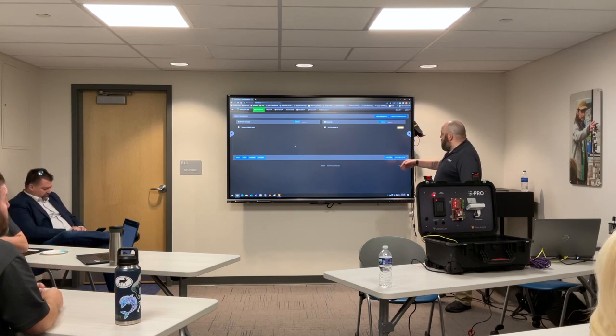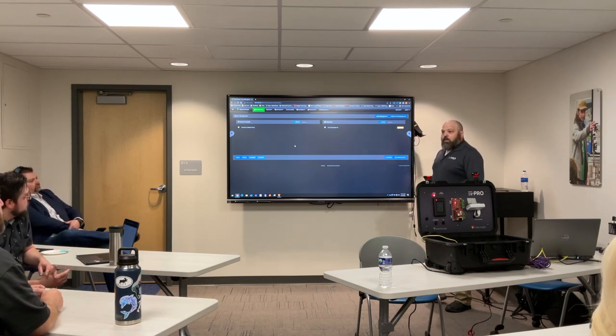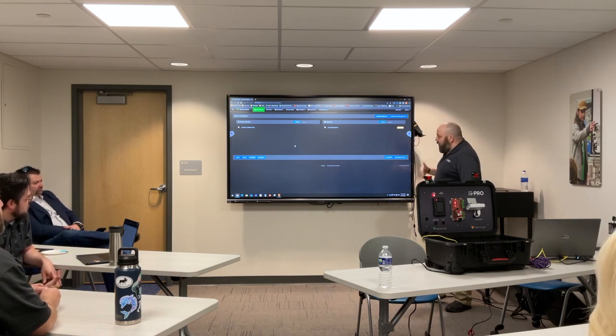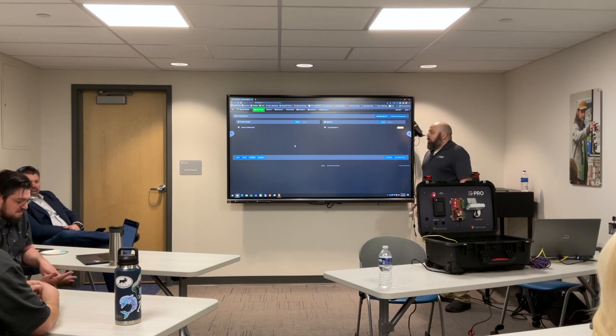So what we found talking to some, mostly hospitals, was that people were coming in and grabbing a whole bunch of opioids off at the pharmacy and they would just run out the door. Because they knew that with the lockdown, the REX was still there, they could just hit the crash bar and keep right on running. So working with them, we developed lockdown with no REX, which was designed for very specific uses, very specific time frames where we could lock down the system. We want to keep people in the spot that they are, so it's there for you.